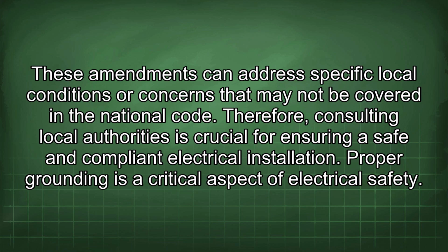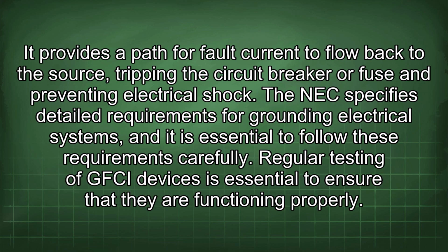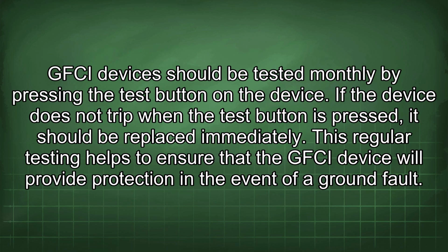Proper grounding is a critical aspect of electrical safety. It provides a path for fault current to flow back to the source, tripping the circuit breaker or fuse and preventing electrical shock. The NEC specifies detailed requirements for grounding electrical systems, and it is essential to follow these requirements carefully. Regular testing of GFCI devices is essential to ensure that they are functioning properly. GFCI devices should be tested monthly by pressing the test button on the device. If the device does not trip when the test button is pressed, it should be replaced immediately. This regular testing helps to ensure that the GFCI device will provide protection in the event of a ground fault.